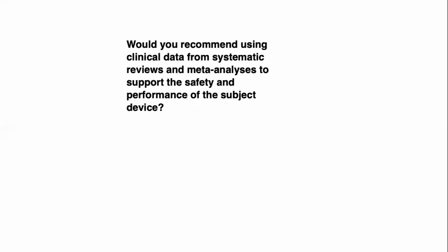The systematic reviews and meta-analyses are useful for the competitive landscape. Pooled data is very useful for establishing safety and performance and acceptance criteria, but not for the subject device.